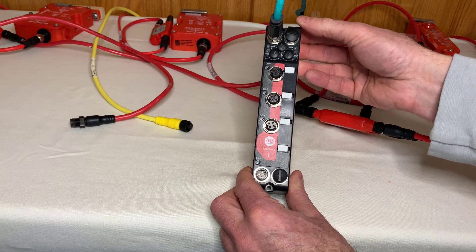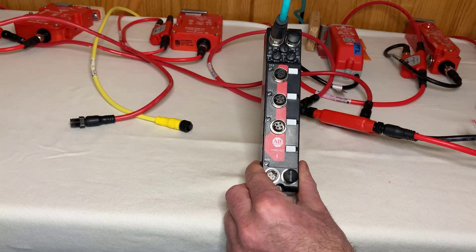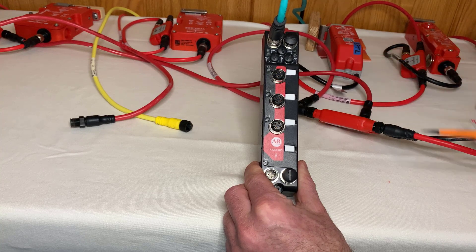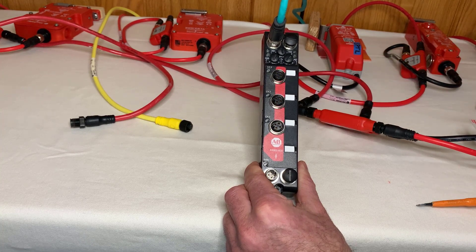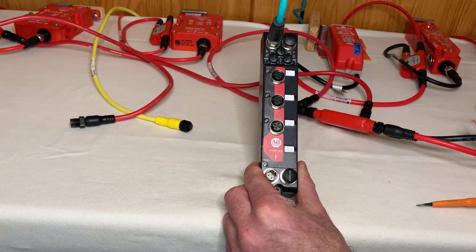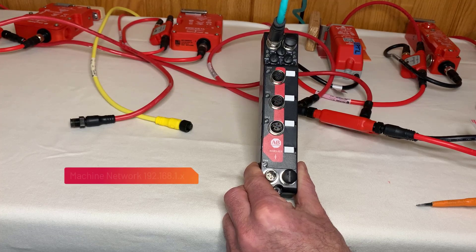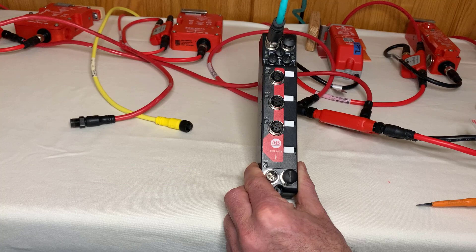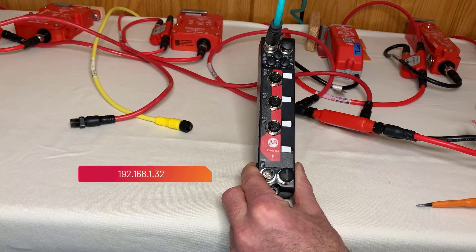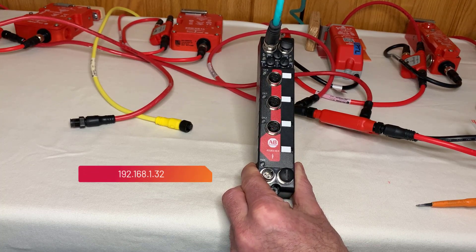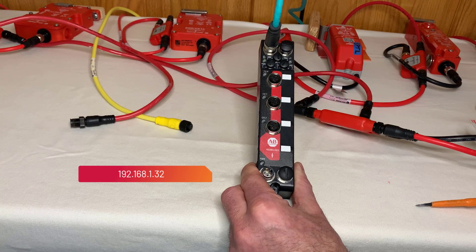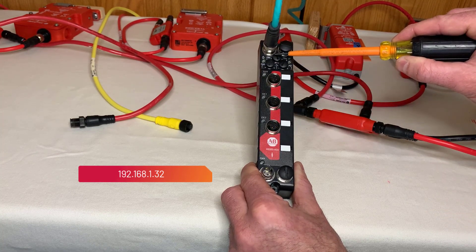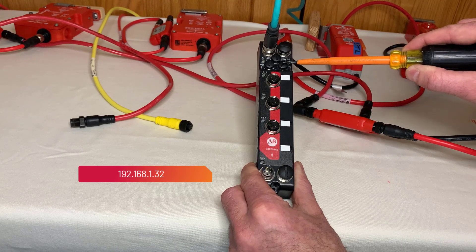Underneath the Ethernet ports are three small covers where the IP address switches are located. Though the device ships DHCP BOOTP enabled, many users choose to use a 192.168.1 machine network. This module has been set to the network address 192.168.1.32 by setting the hundreds to 0, tens to 3, and ones to 2.